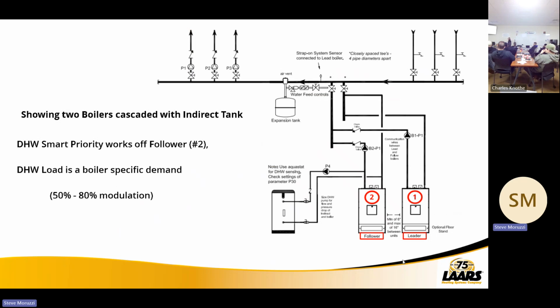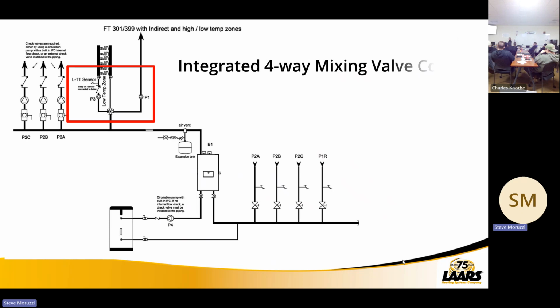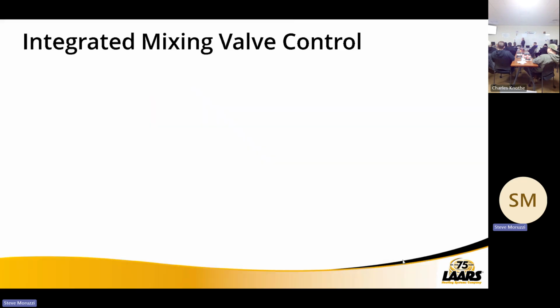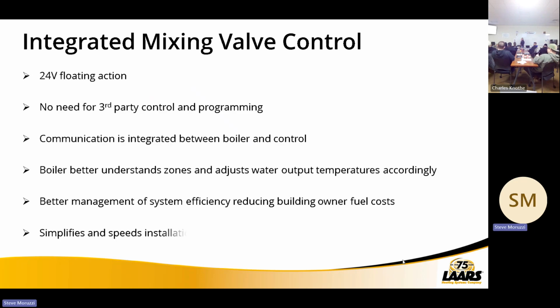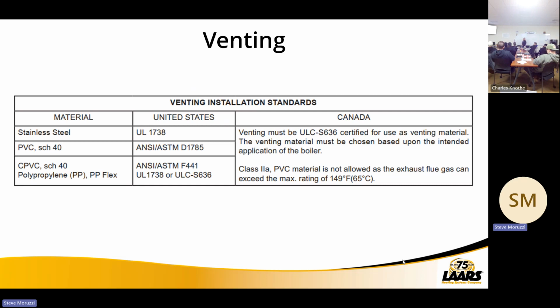And then we could do the same with cascading. And your indirect tank comes off the follower or member boiler. So just follow these installation instructions in the I&O manuals as well. And the low temp zone with a mixing valve, follow that as well, and how to wire that up and operate that. So again, that mixing valve, we provide the 24 volts. No third party needed for the control of programming. Now we can see a better understanding and adjust the water temperatures output accordingly. So we're able to manage this a lot better, and it simplifies the installation quite a bit.